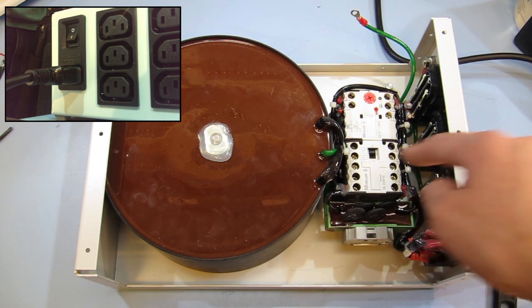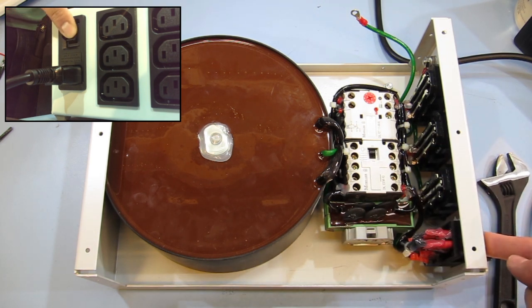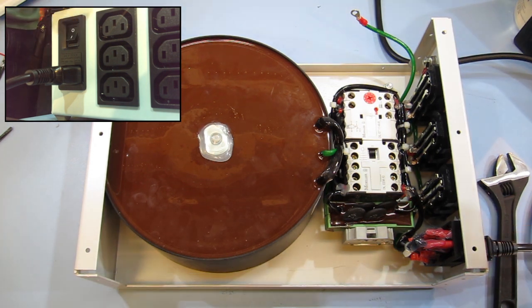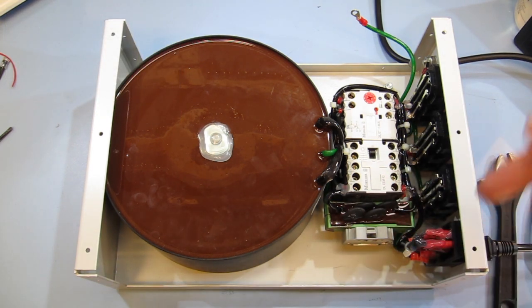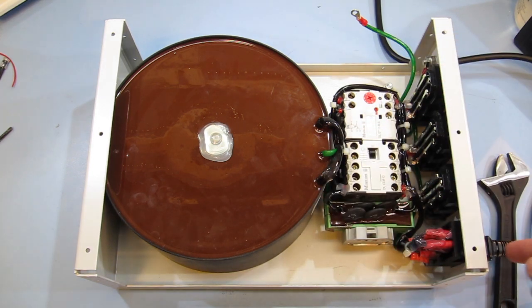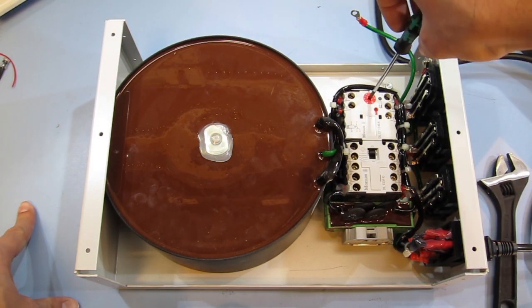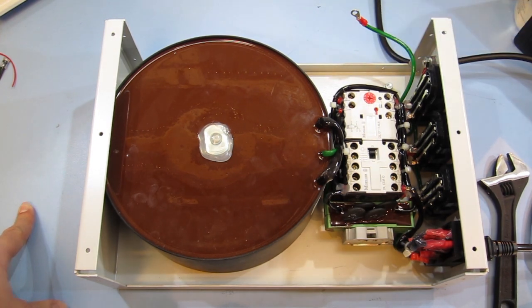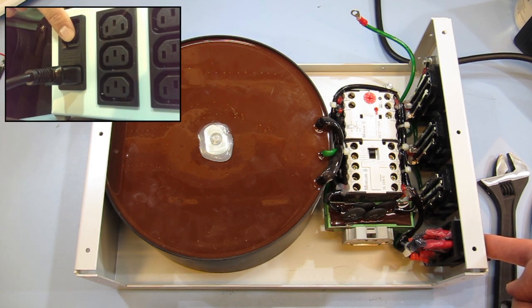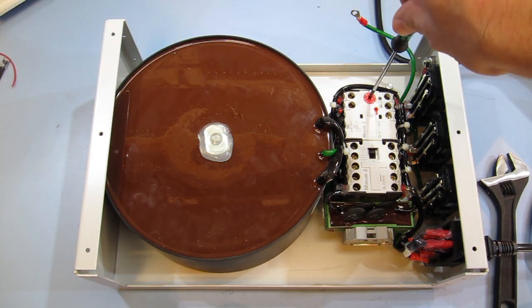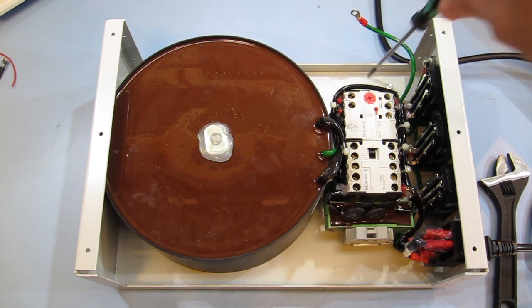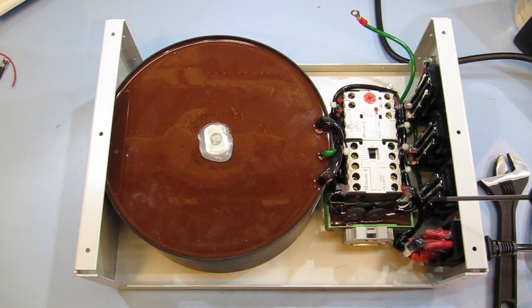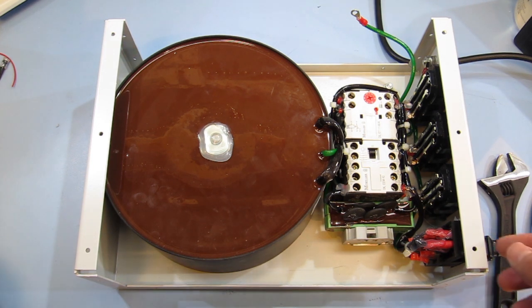I don't know if you can see that, but some of these screws are actually moving when the contactor clicks in and out. Those don't appear to have any wires in the terminals, but it's probably worth just doing those up so they don't come loose and end up rolling around inside. But we can just check. If I set this dial to 10, that's probably the equivalent of 1 second. If I turn it on now, yeah, that seems about right, so that's about a second. I don't know if they calculated 300 milliseconds from anywhere. Maybe that means that the rating of these NTCs can't be exceeded even if you have a load plugged in. I don't know, but I'll set it back to 300, that seems fine.